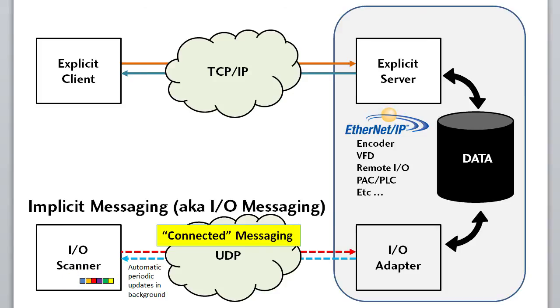Implicit connected message delivery isn't guaranteed because it's UDP, but if you don't get a drive speed or amperage update when you are getting several per second, it's not a big deal if you miss one every now and then.